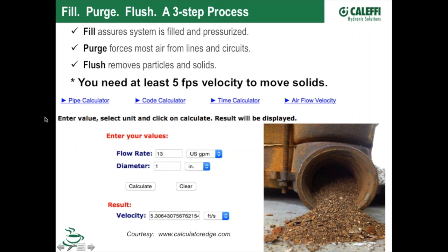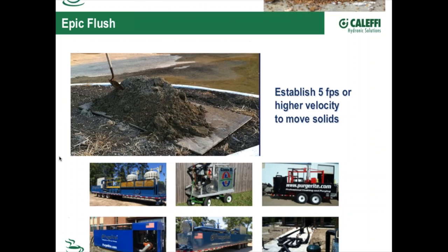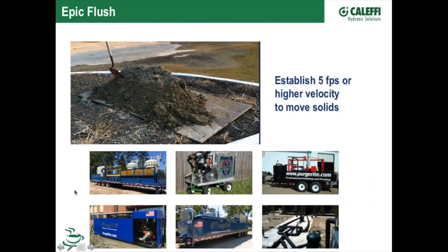So just make sure that the valve that you're filling with has the ability to do that if you're concerned about flushing this type of material out, because 5 gallon minute flow right through a fill valve, sometimes you might need to bypass that. This really hit home for me a couple years ago. We had a booth at the IGSHPA ground source heat pump show down in Tulsa, and I was walking around just checking the other booths, getting to know people and meet people, and I came across this company here called PurgeRite. And I said, well, what do you guys do?